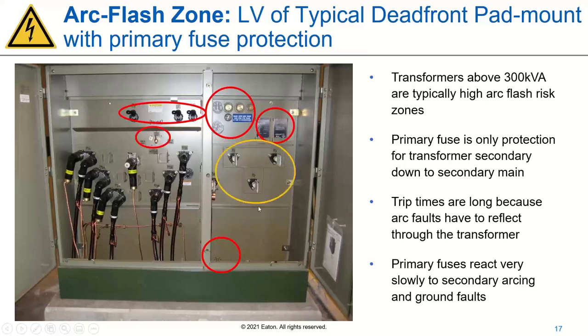All of this is very close to the arc flash hazard zone. And with the way the standards are currently written, you've got to open this low voltage compartment first before even being able to get to high voltage. And you may think high voltage is more dangerous, there's more energy there. To a certain degree, that is correct. But with the dead front primaries that are very common on transformers, we see that as a much lower arc risk zone, versus the amount of energy that's present in these live front connections.